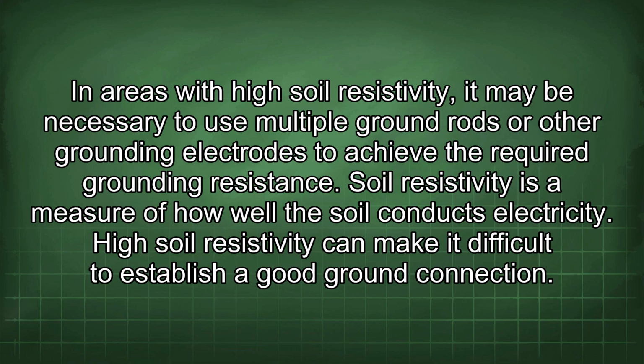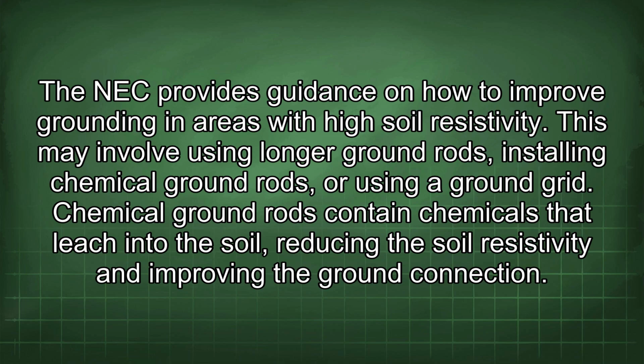Soil resistivity is a measure of how well the soil conducts electricity. High soil resistivity can make it difficult to establish a good ground connection. The NEC provides guidance on how to improve grounding in areas with high soil resistivity. This may involve using longer ground rods, installing chemical ground rods, or using a ground grid. Chemical ground rods contain chemicals that leach into the soil, reducing the soil resistivity and improving the ground connection.